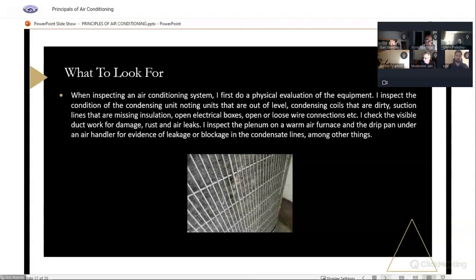So I'm going to tell you what I look at when I inspect air conditioning systems. My mindset is that we have a state standard, and I'm trying to follow that. No matter what anybody knows about anything electrical, plumbing, heating, our job is to determine if the system's working or not, and what condition it may be in as far as needing maintenance. There are some telltale signs when a system is not operating, but first I do a physical evaluation. I look at the outside first, because I start on the outside. So, you look at the condensing unit, noting if it's out of level. If the unit's out of level, there is oil in the base of the compressor. That oil is going to run lopsided, and it may not be lubing parts in that compressor properly. And eventually that can cause a failure.